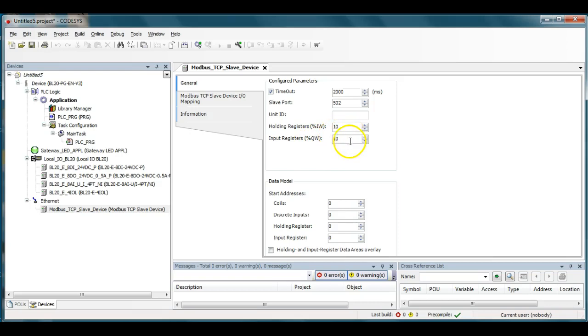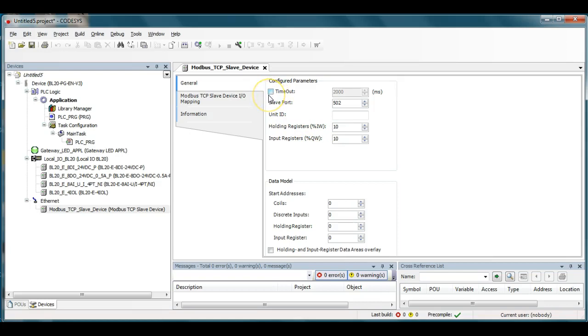Turck supports up to 1024 holding registers and 1024 input registers. If you need to transfer more data than that with the Turck device there's no other way to do it in Modbus: 1024 words input and 1024 words output. One thing I have learned about this is that you should uncheck this because otherwise if your master stops pinging or polling the device after two seconds the Turck device will automatically reset the outputs to zero. So I'm going to turn that off to keep it so it shows all the states.